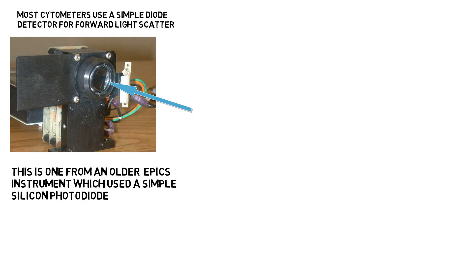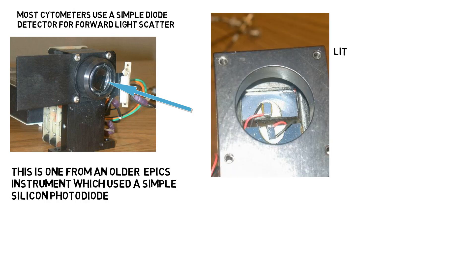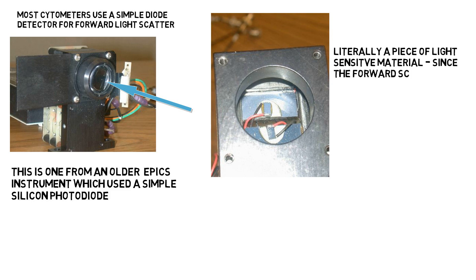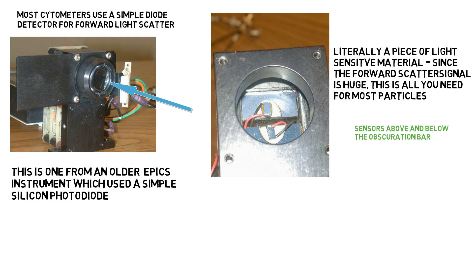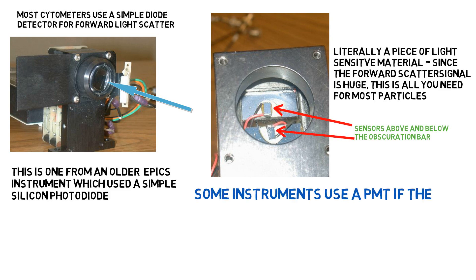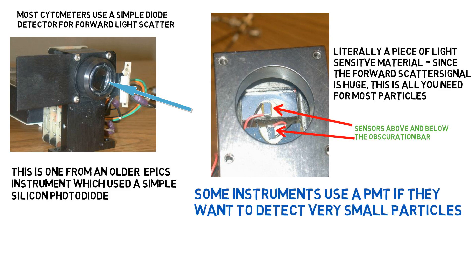Most flow cytometers use a simple diode detector for forward light scatter. This one is from an older EPICS instrument, which used a simple silicon photodiode — literally a piece of light-sensitive material. Since the forward scatter signal is huge, this is all you need for most particles. You can see the sensors above and below the obscuration bar. Some instruments do use PMTs if they want to detect very small particles.